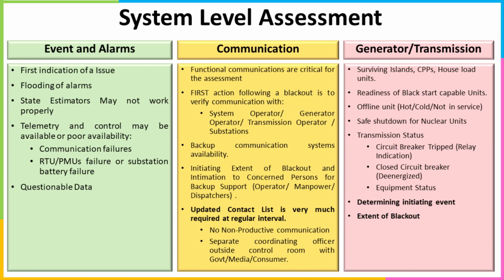You should also look into the initiating event, the extent of the blackout, and what things have resulted. During such a wartime scenario, there will be multiple queries brought to you. Many phone calls will be received by the control center. So the operator who is restoring the system should be kept away from non-productive communication. And there will be a requirement for a separate coordinating officer at the control room center, who can interact with the government, media, and consumers, so that they can be provided the information under those scenarios.